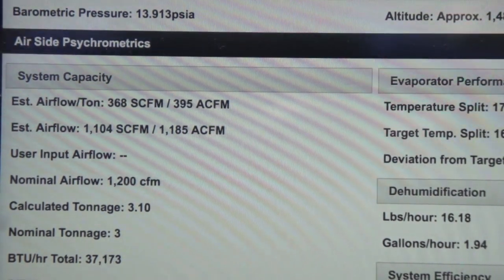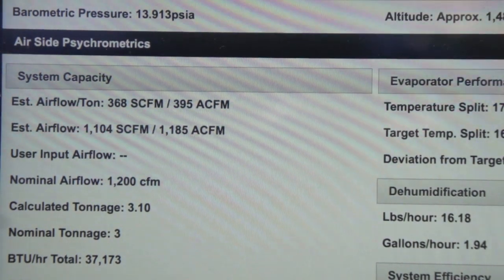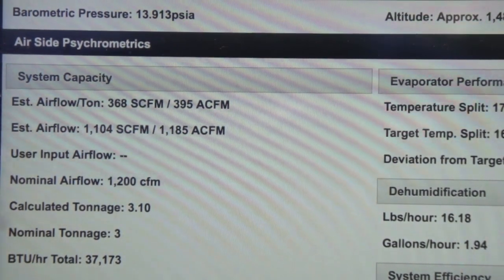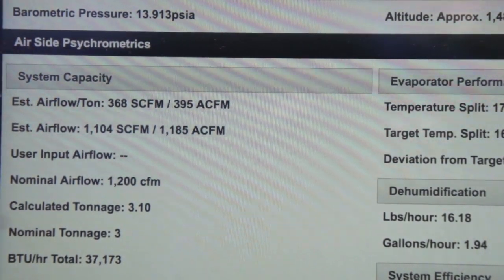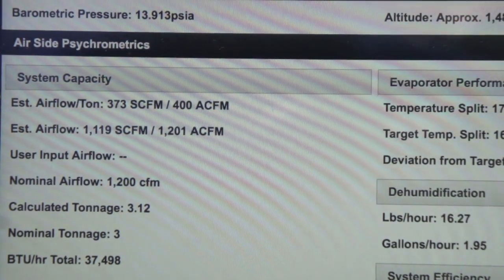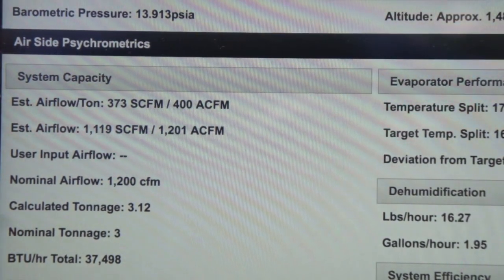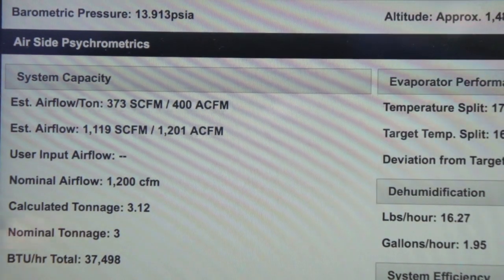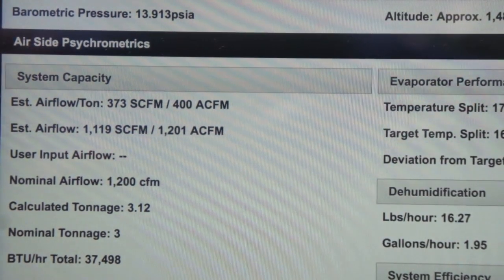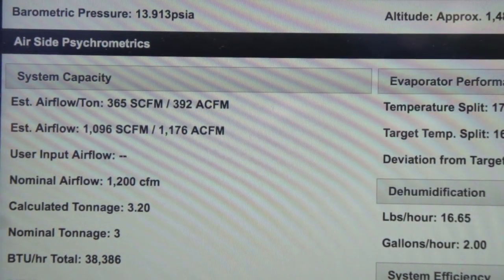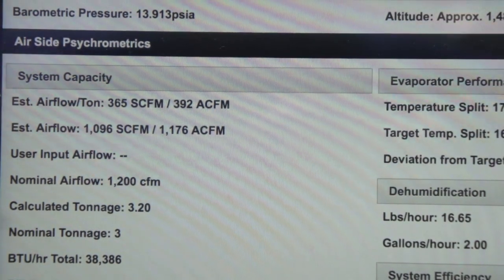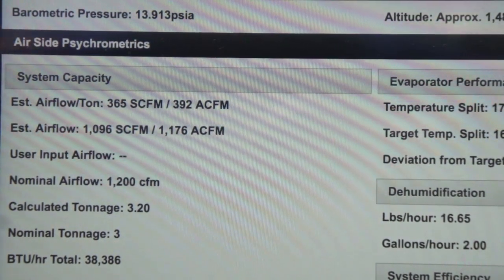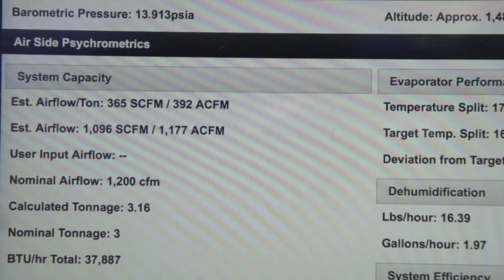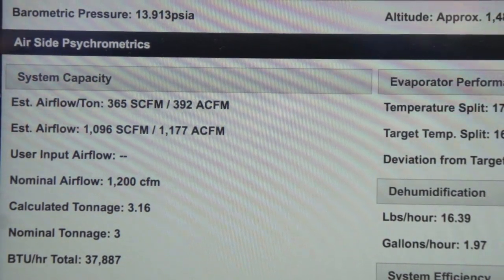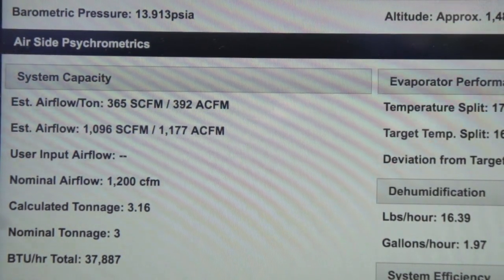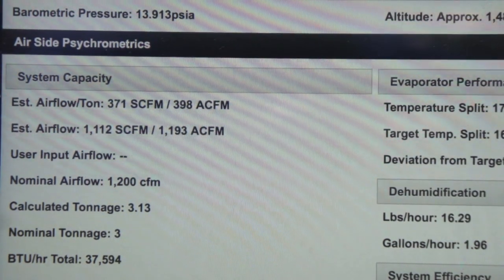The difference between actual airflow and standard CFM is that a standard CFM means a CFM of air that is at 68 degrees Fahrenheit, 0% relative humidity at sea level. It's that density of air. It's 0.075 pounds per cubic foot. On air conditioning, we're supposed to have a nominal 400 CFM per ton. So that nominal 400 CFM per ton is our target airflow for cooling.